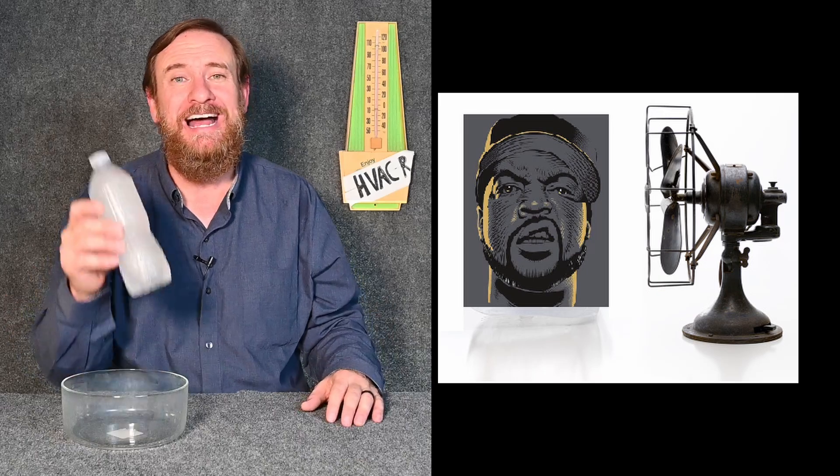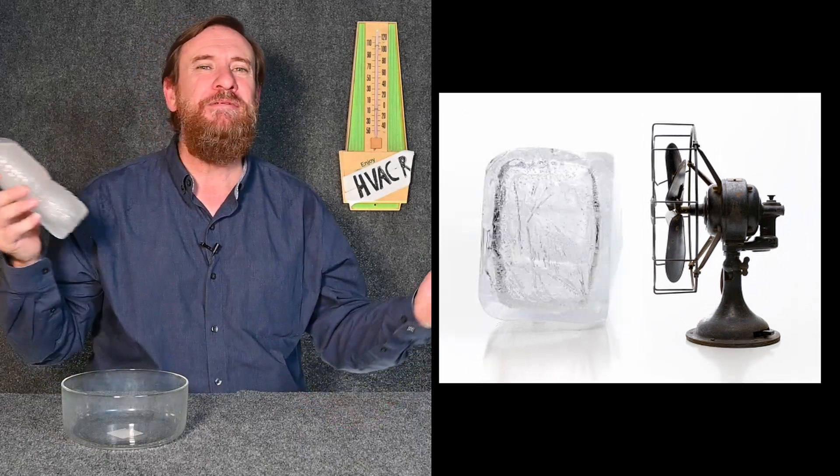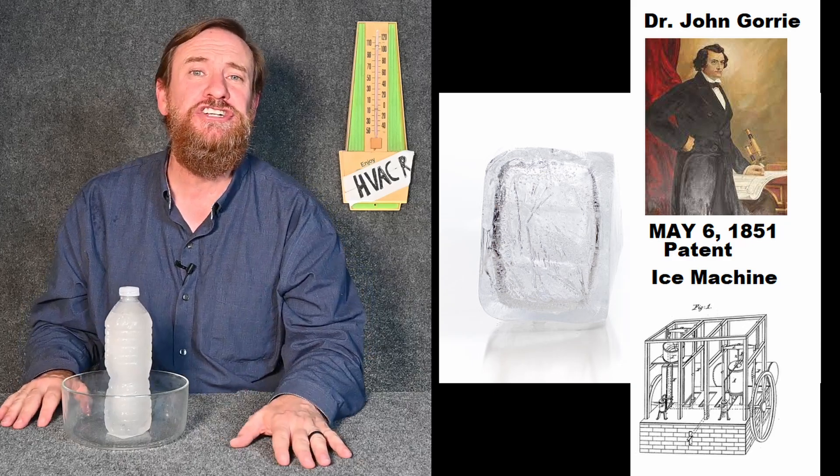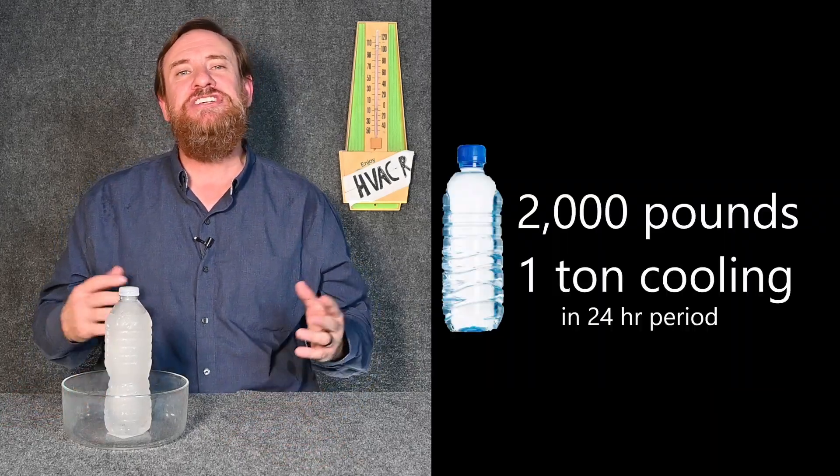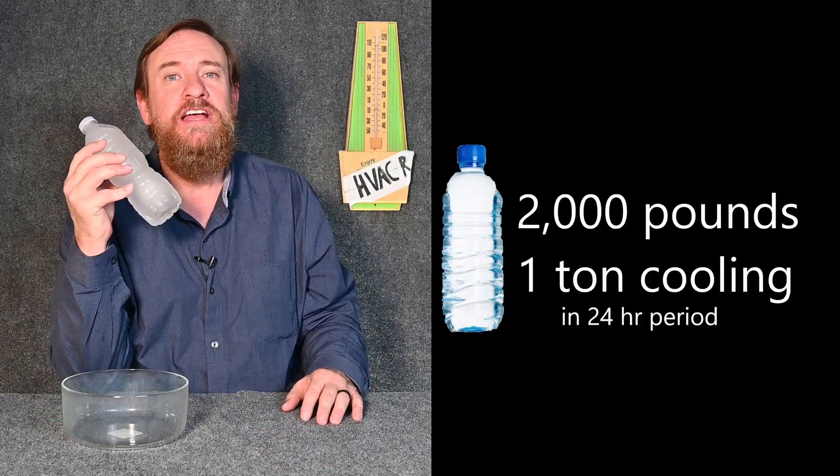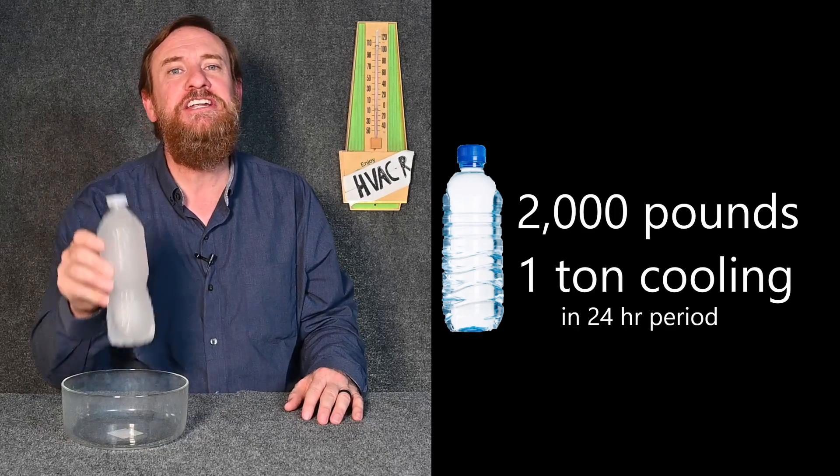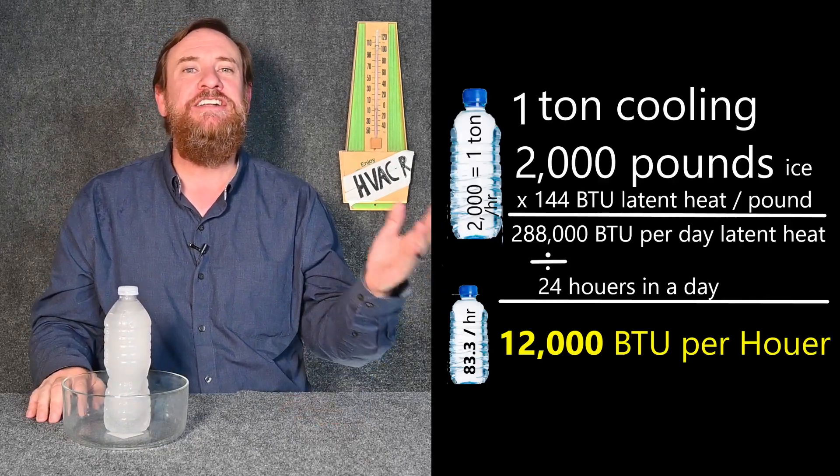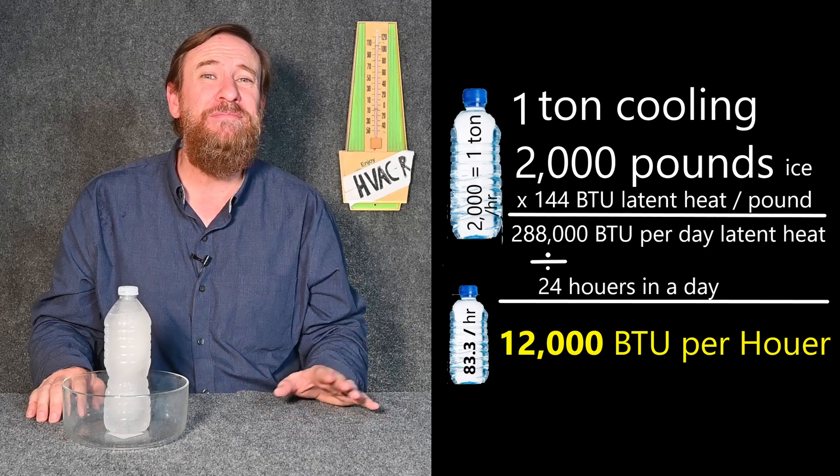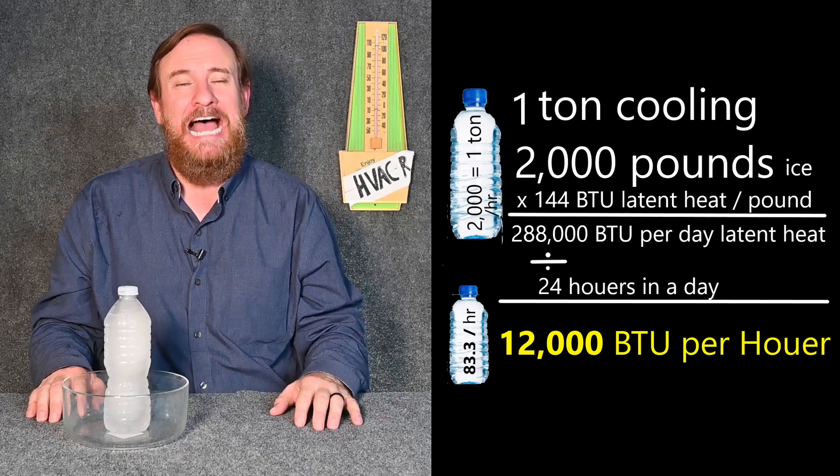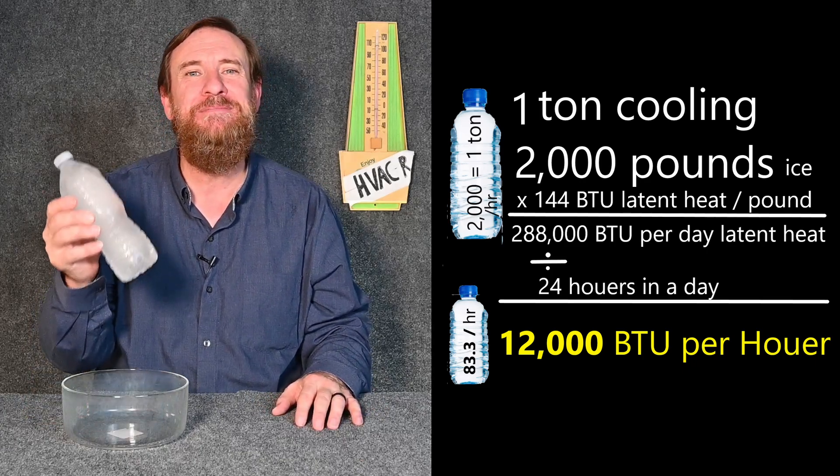So yes, cooling by ice is absolutely possible. It's actually refrigeration got its start with John Gorrie before the air conditioner was even invented. And we actually sized air conditioners over tons of ice melting in a 24-hour period. We can actually divide that down. It comes to 12,000 BTUs in a one-hour period. So it still comes back to melting ice.